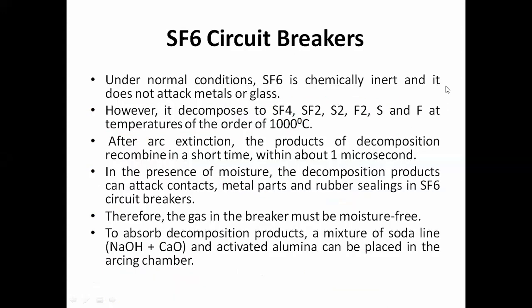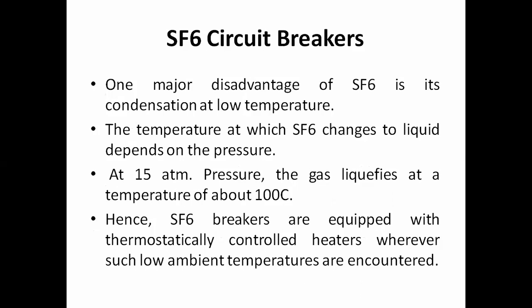So due to these properties, we basically use the SF6 circuit breaker, in which sulfur hexafluoride is used as the gas. Under normal conditions, SF6 is chemically inert and it does not attack, which I have already discussed with you. And due to these certain properties of sulfur hexafluoride gas, we use this type of circuit breaker in order to separate the system when it becomes faulty. Okay. But there are certain disadvantages.